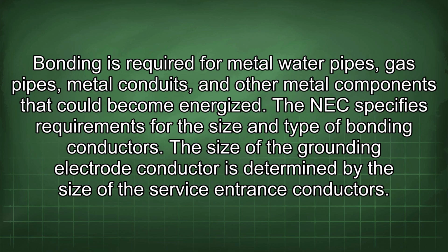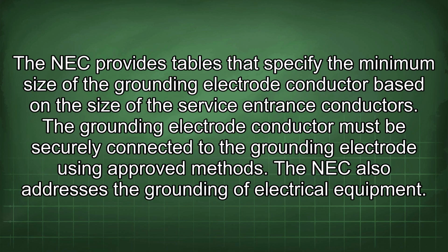The size of the grounding electrode conductor is determined by the size of the service entrance conductors. The NEC provides tables that specify the minimum size of the grounding electrode conductor based on the size of the service entrance conductors. The grounding electrode conductor must be securely connected to the grounding electrode using approved methods.